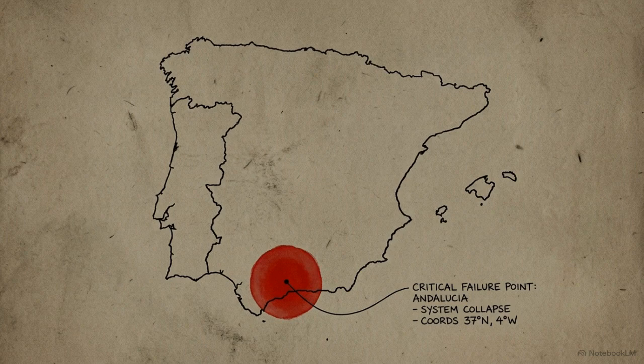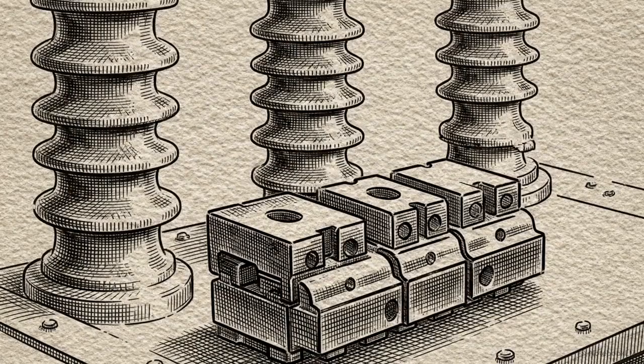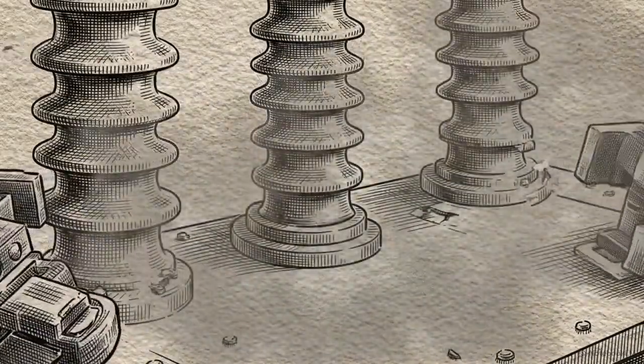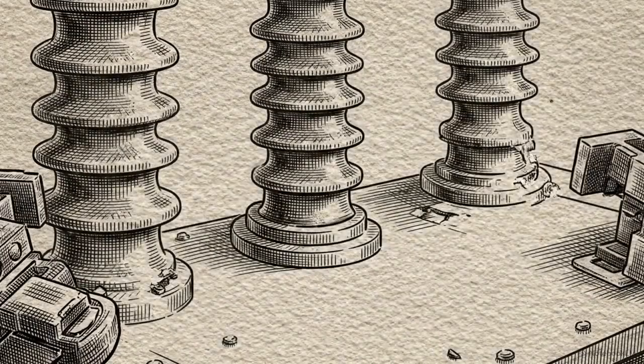57 seconds later, the localized voltage spike first reached a critical threshold in the Granada region. A 400 to 220 kilovolt transformer tripped offline due to its overvoltage protection. This instantly cut off 165 megavolt amperes reactive, or MVAR, of vital reactive energy absorption.